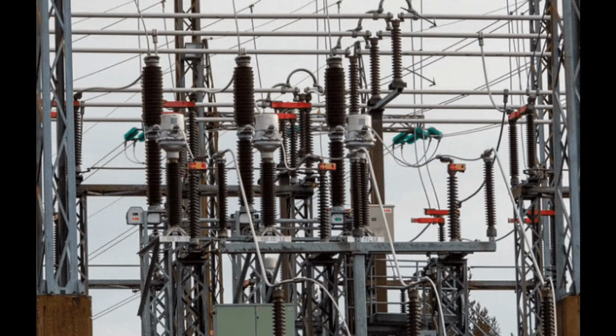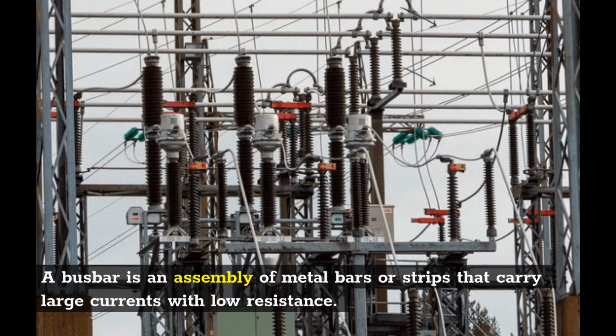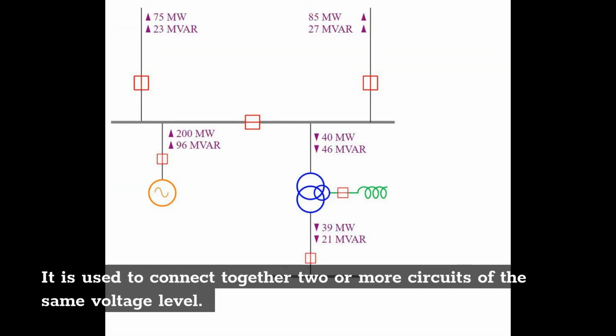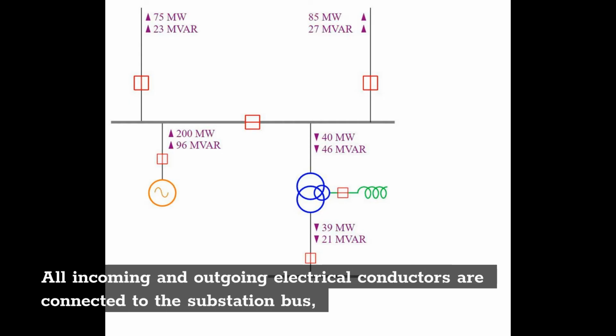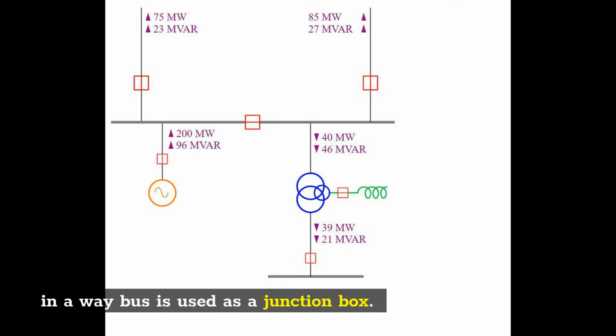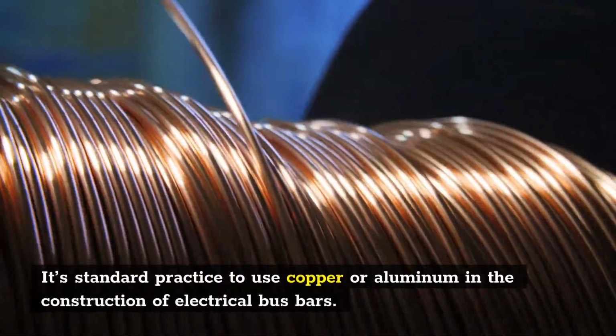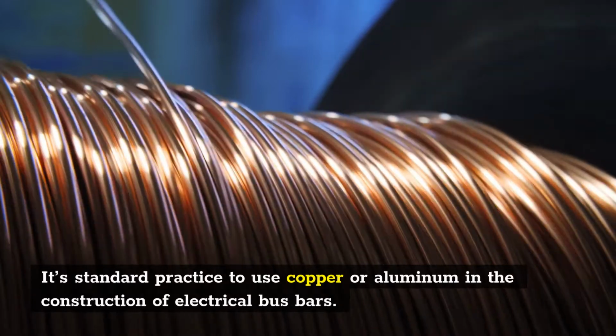Substation busbar. A busbar is an assembly of metal bars or strips that carry large currents with low resistance. It is used to connect together two or more circuits of the same voltage level. All incoming and outgoing electrical conductors are connected to the substation bus. In a way, the bus is used as a junction box. It's standard practice to use copper or aluminum in the construction of electrical busbars.